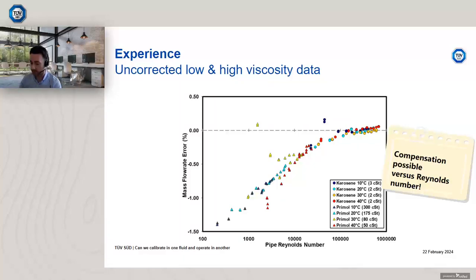We have conducted a lot of research with a lot of Coriolis meters of different sizes, different manufacturers, and different fluid Reynolds numbers by changing the viscosity, changing the velocity, and the density. And we can categorically state that when we do witness Reynolds number effects, they do appear to be linear. So compensation certainly appears to be possible. We find that the Reynolds number effect is repeatable and reproducible, such that if we change out fluid and then go back to that same Reynolds number, which you can see we've achieved here, we still get the same deviation, which is very good.